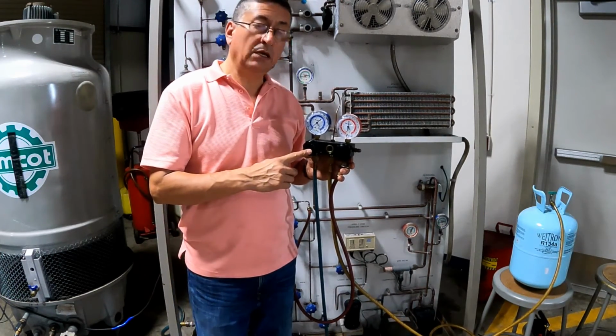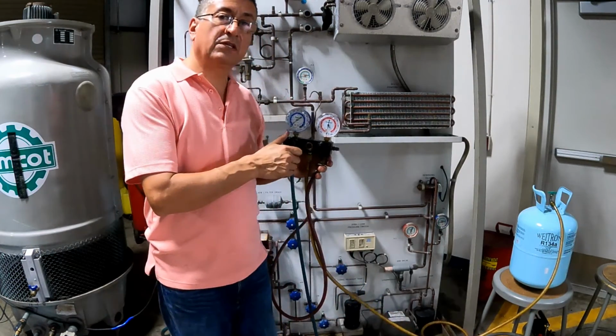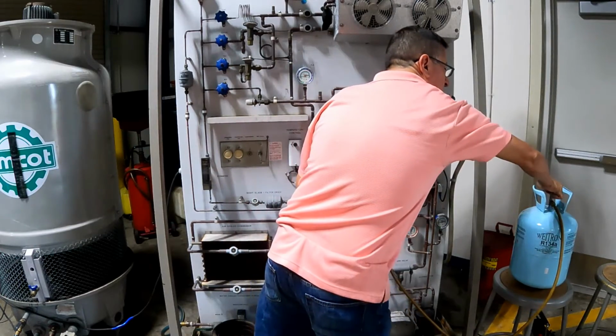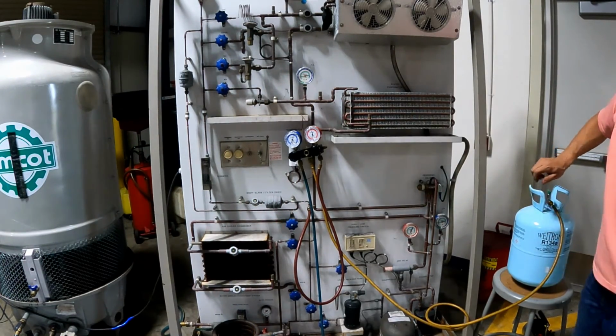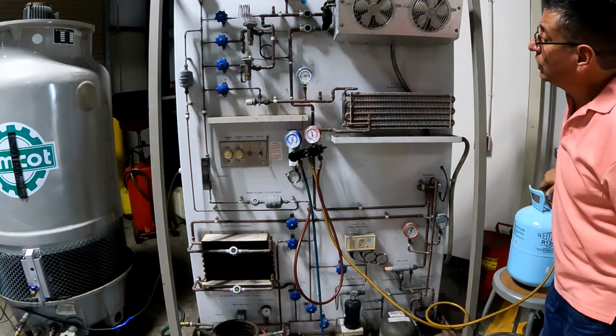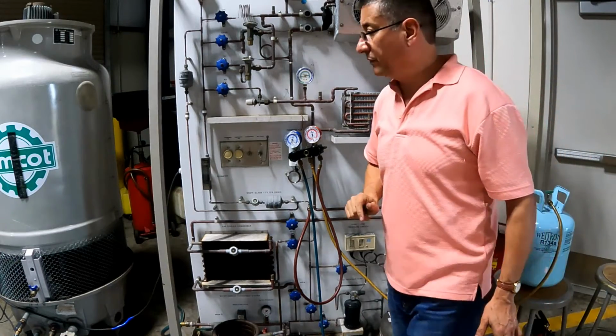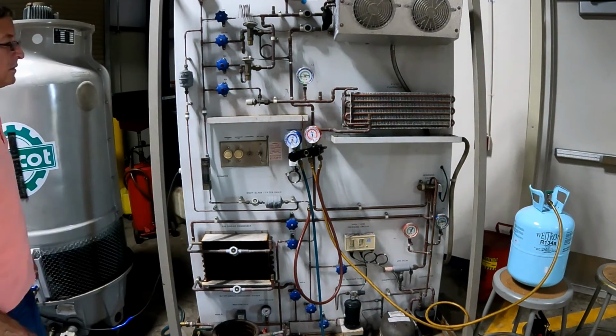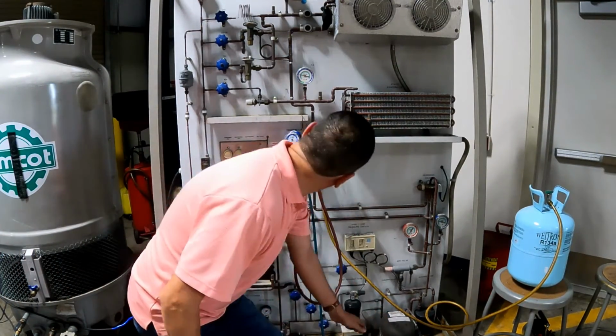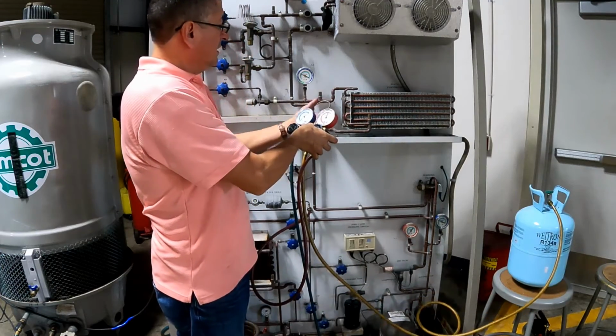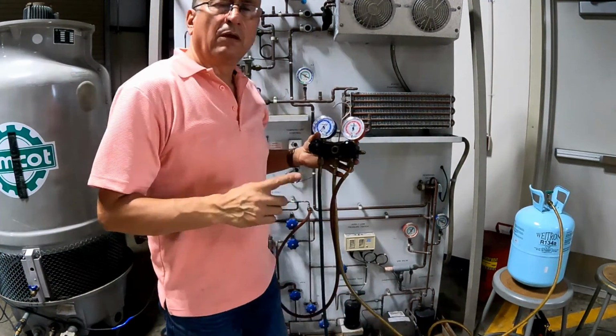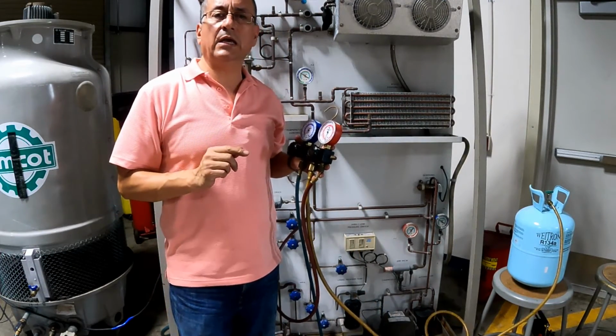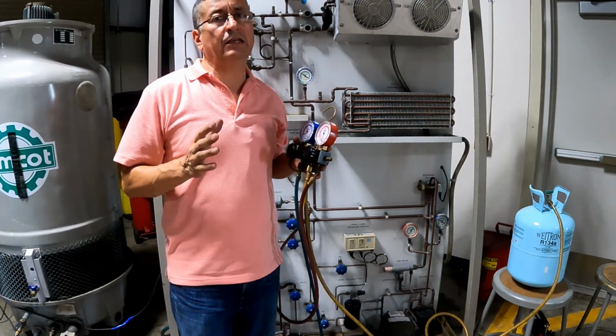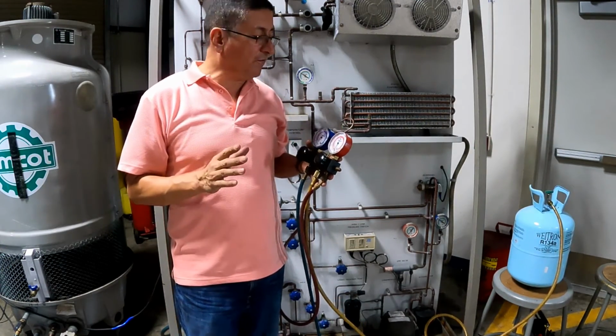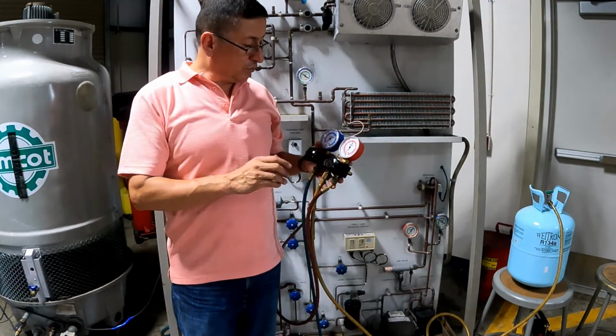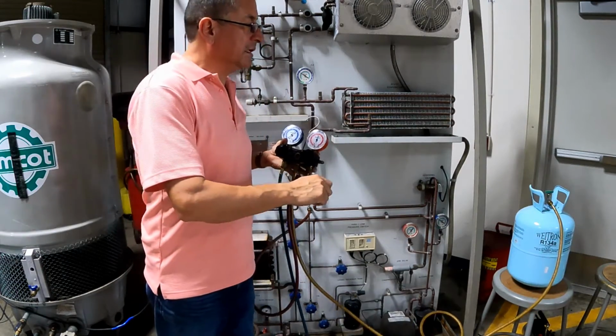Because in this moment the unit is empty, we are going to add a little amount of refrigerant into the system. We are going to open that one and open the cylinder to add refrigerant. And now we are going to close again, and we are going to start the system. Remember, for R134A, the low pressure side should be around 55-60 psi, and the high pressure side in between 225 and 280 psi. Okay, we are going to check right now. We are going to add refrigerant.